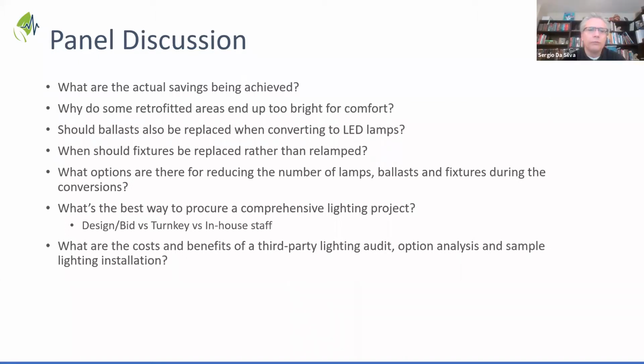The simple answer in most instances, for the purpose of optimizing performance, is yes. But there are instances where the ballast is new, you've tested a combination of various manufacturers' lamps with the existing ballasts, they're in good condition, they operate. But the concern is that if you don't have a uniform installation where you can verify the date codes and the manufacturer of the ballasts on site, and can't confirm they're going to perform from wing to wing, floor to floor, you run the risk of needing to supplement the installation with additional ballasts during your project.